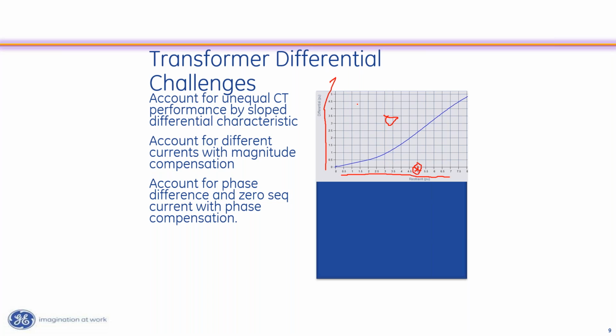And my differential, because it's a 5 per unit fault, is up here. So my actual point is right there. For that legitimate fault, I would operate. Now, let's talk about what would happen for that out-of-zone fault, right? Well, that out-of-zone fault that I mentioned, I said we had 10 per unit and 6 per unit.